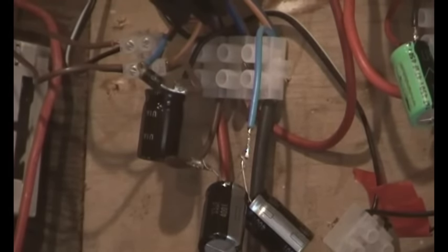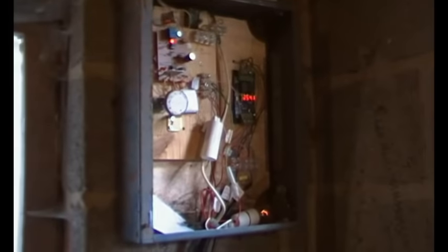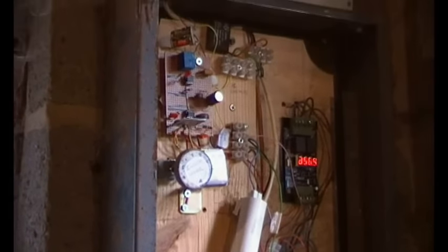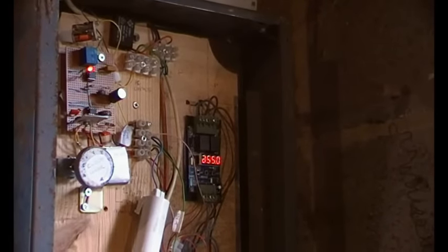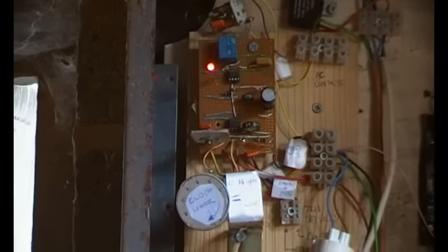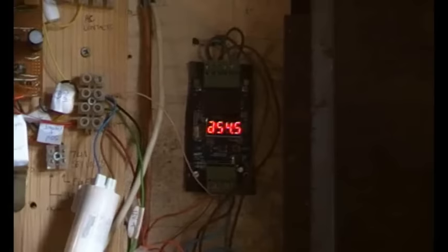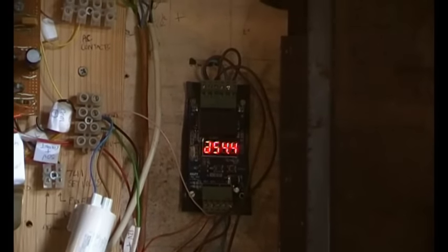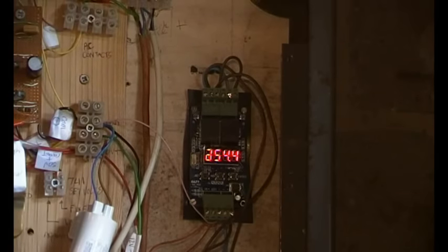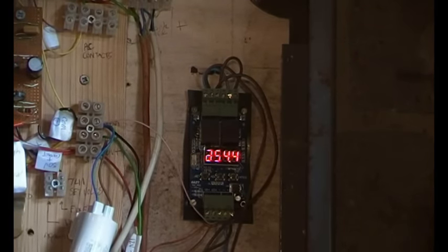I've taken the door temporarily off the charge controller box and the charge controller just clicked out and back on again. Next to it we've installed the timer relay. There's the stage one as I call it - that's the original - and next to it is the voltage detecting timer relay. It's got two circuits in there and it's very important that both of those circuits are tuned correctly. I think I need to do a drawing about this so you can get a full idea of what's going on.